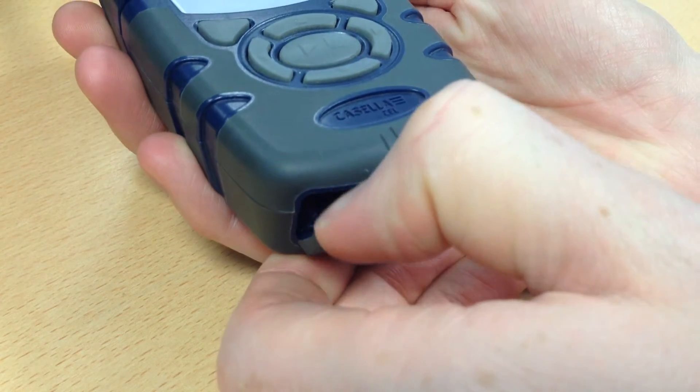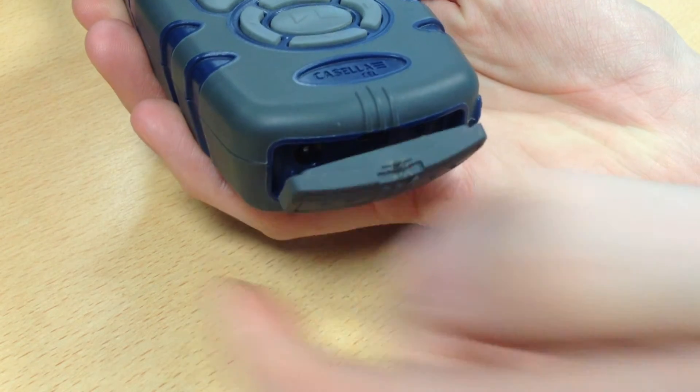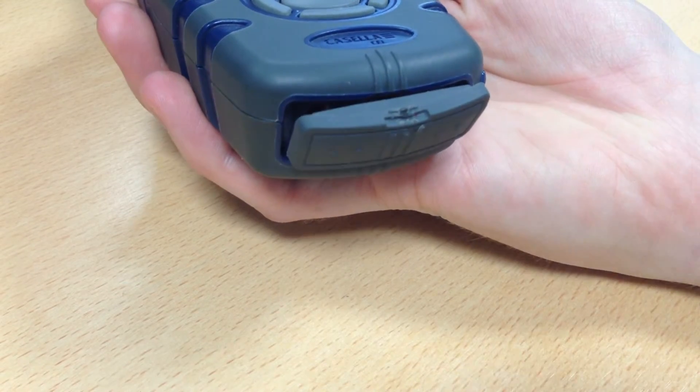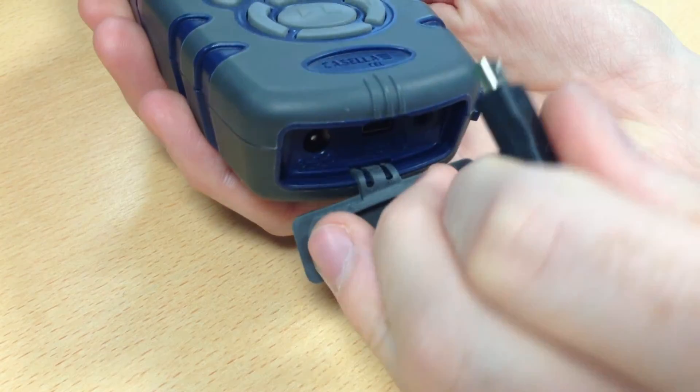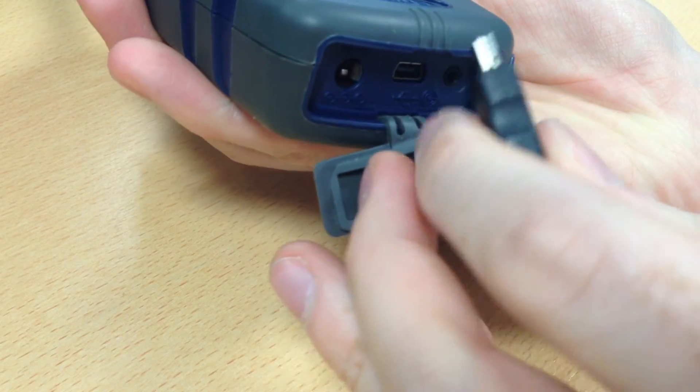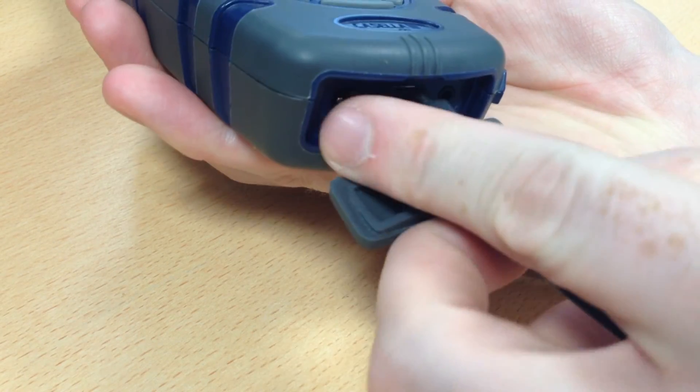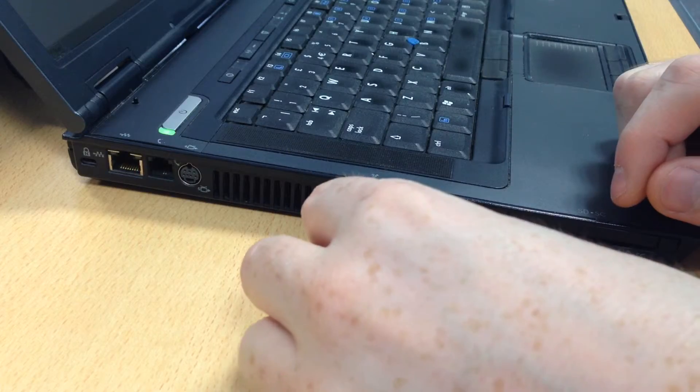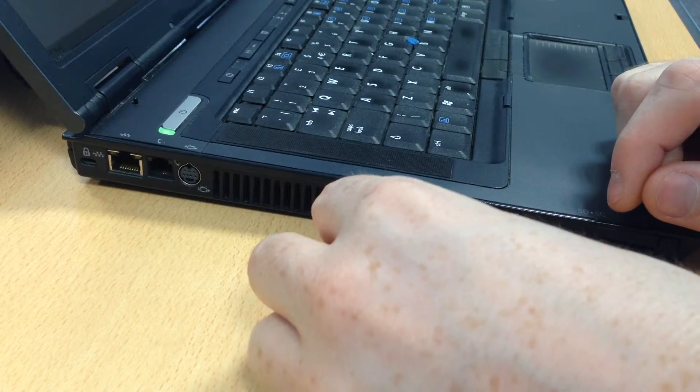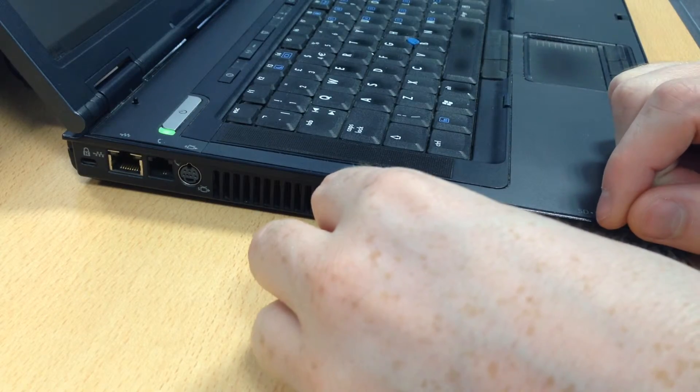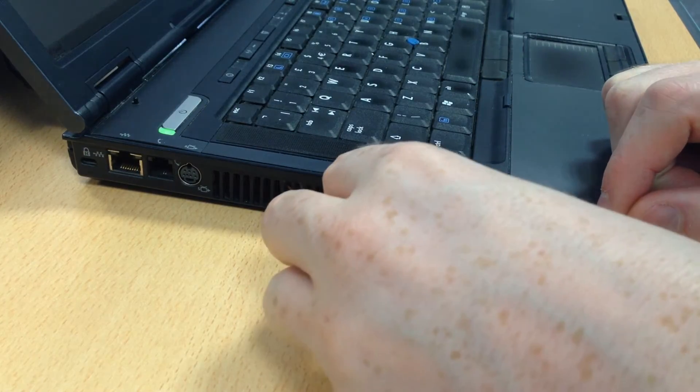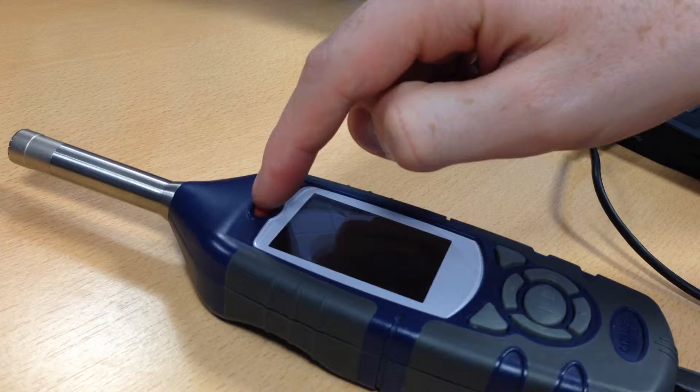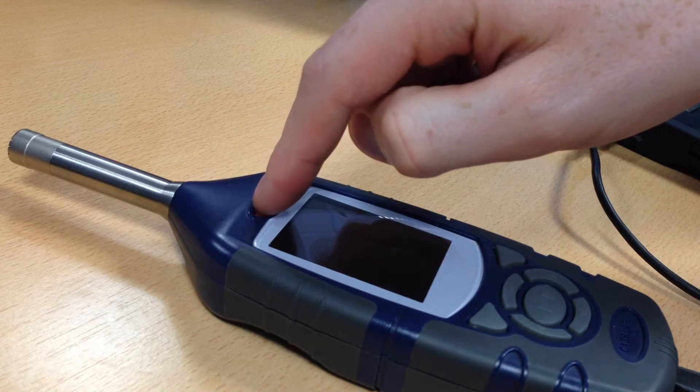Once Casella Insight has been set up correctly, plug the Mini-B end of the USB cable into the bottom of the instrument. Now plug the other end of the cable into an available USB slot on your computer and power the instrument on by pressing the red power button.